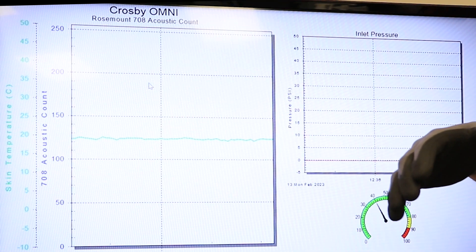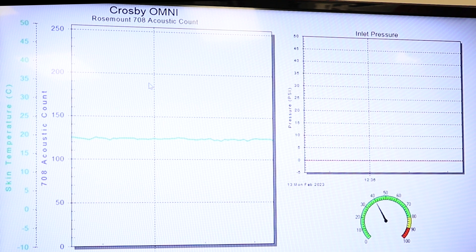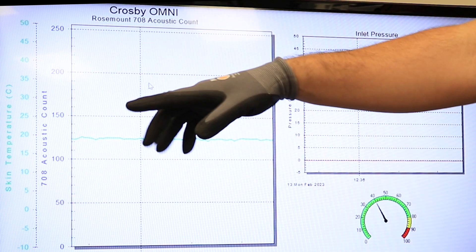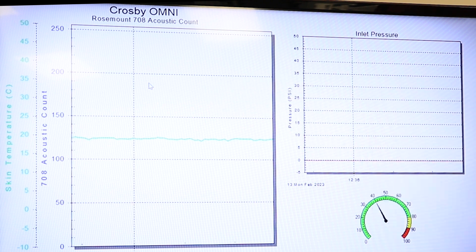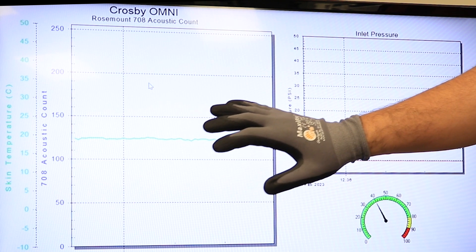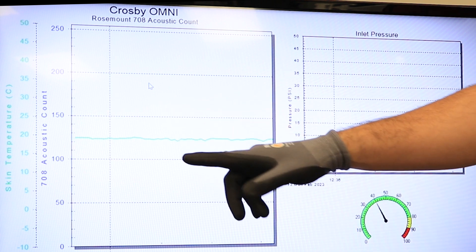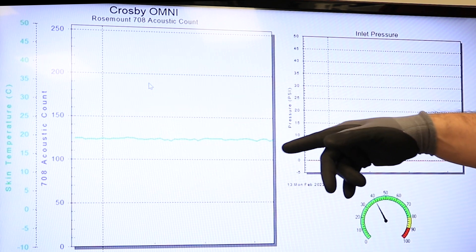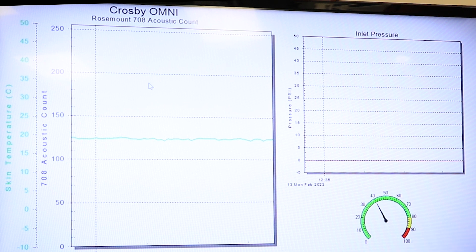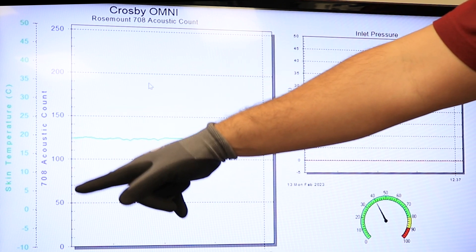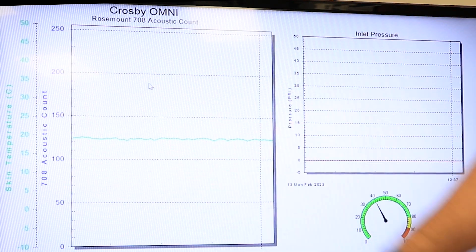This will indicate when there's acoustic turbulence at the outlet of the pipe. In green, we're graphing the skin pipe temperature also at the outlet piping of the PRV. For our demonstration, since we're using compressed air at ambient temperatures, there will not be a change in skin pipe temperature. But in the real world scenario, when we have a temperature or product that is hot or cold, we will see a rate of change accompanying the acoustic count change.